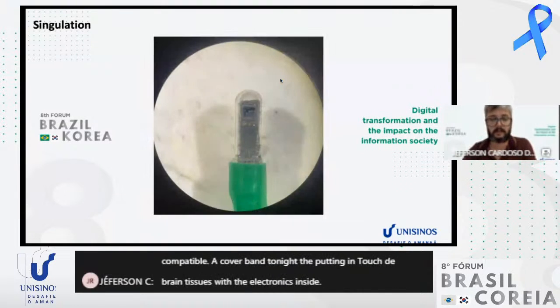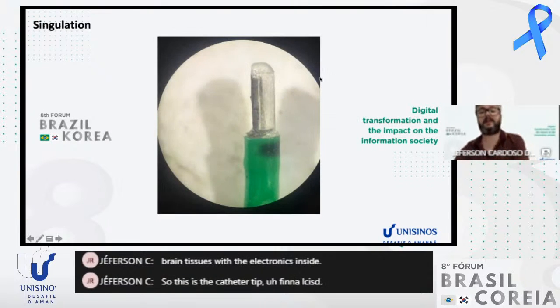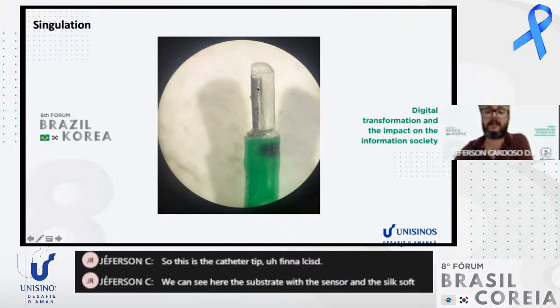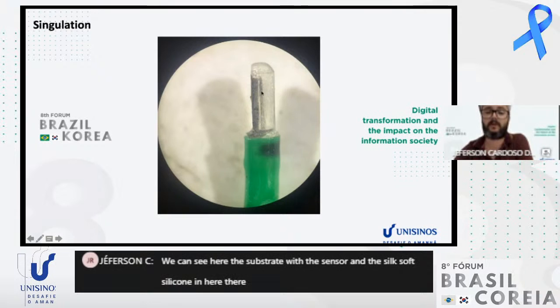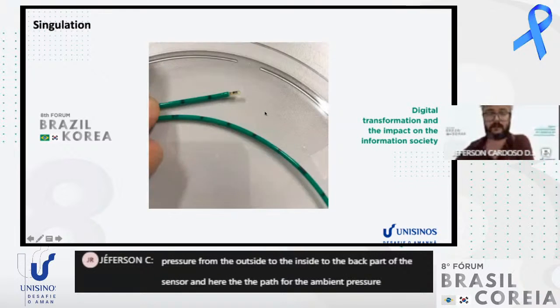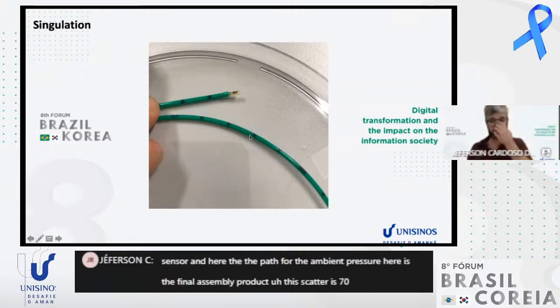So this is the catheter tip finalized. We can see here the substrate with the sensor and the soft silicone, and here there is a venting hole to connect the ambient pressure from the outside to the inside, to the back part of the sensor. Here is the path for the ambient pressure, and here is the final assembled product. This catheter is 70 centimeters in length with a diameter of 1.5 millimeters.